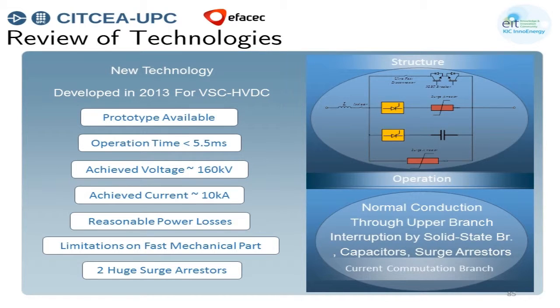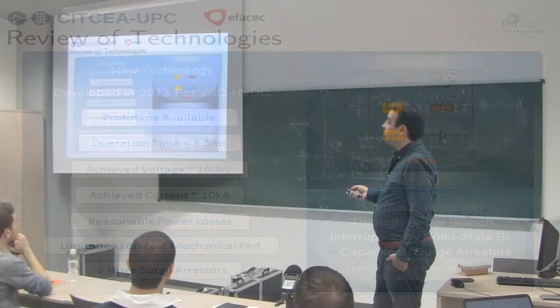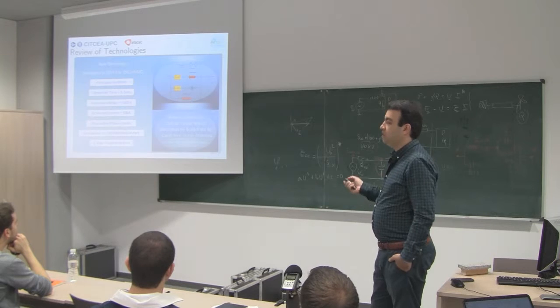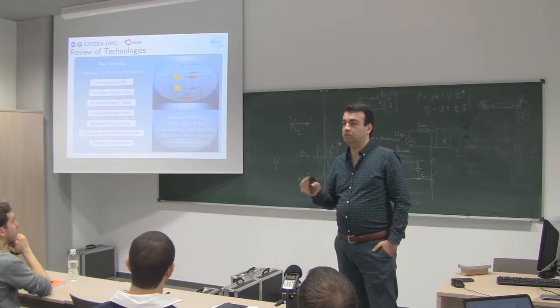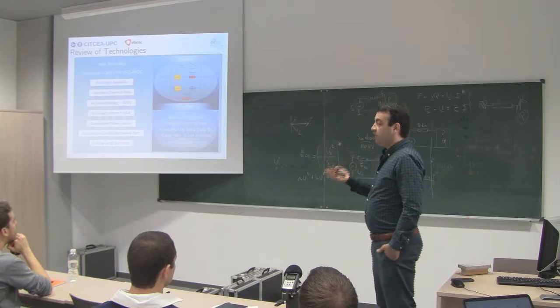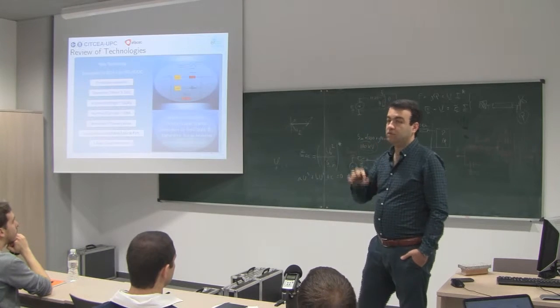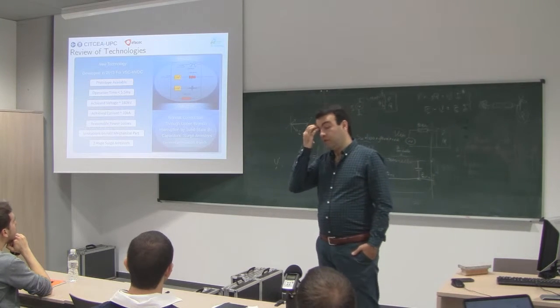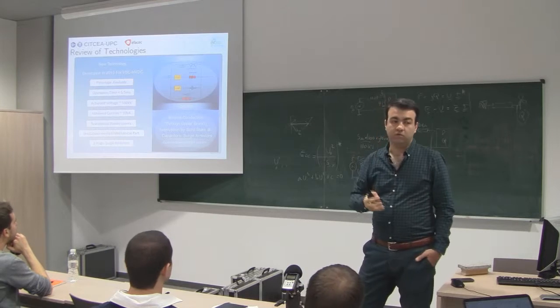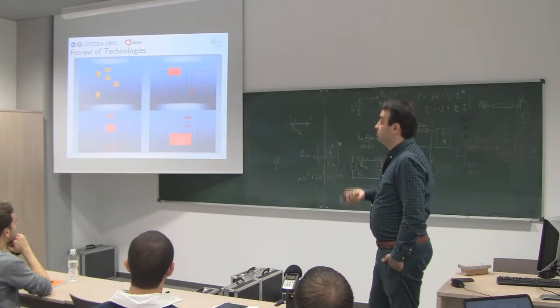So just to highlight that, the operation time for this kind of breaker is identified to be less than 3 milliseconds, which is quite good for multi-terminal HVDC grid protection. And for this one it is around 5 milliseconds, which is again almost good. But if we have other solutions much faster than this, it will be better, because we will save our converters and other vulnerable components rapidly.